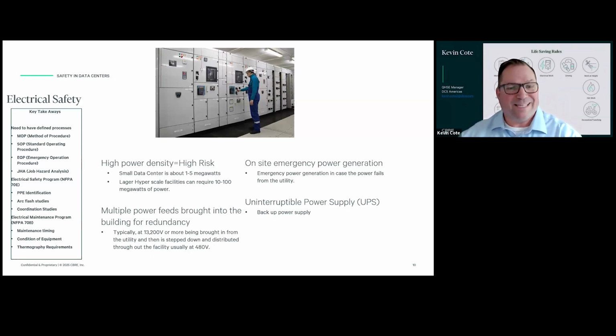There's a certain amount of time it takes for the generators to power up, spool up, and start creating energy. It's a fraction of a second, but you don't want your data to be lost, so that's why there's a battery backup. Generally the battery backup is good for about 15 minutes, though the actual switchover is just a fraction of a second. If you've ever been somewhere and the power dropped, the lights blinked out and came back on, we don't want that in the data center. We want power all the time, so you'll see UPSs and batteries on site.